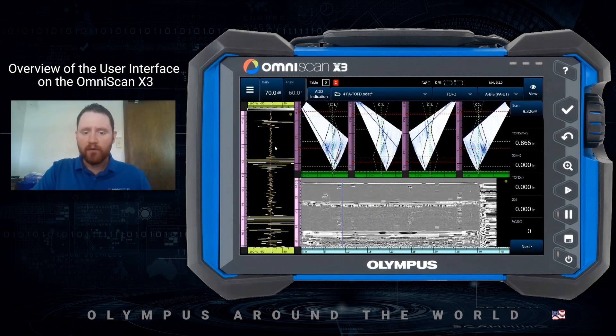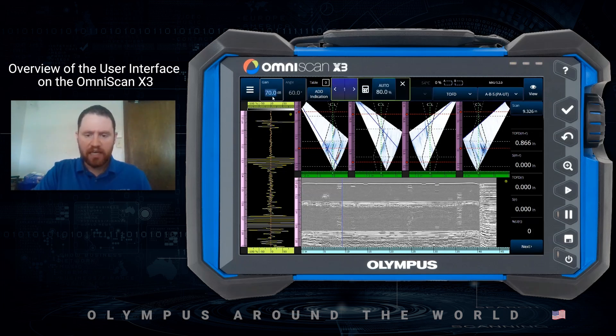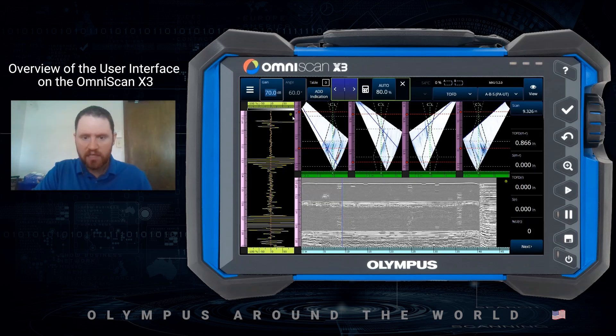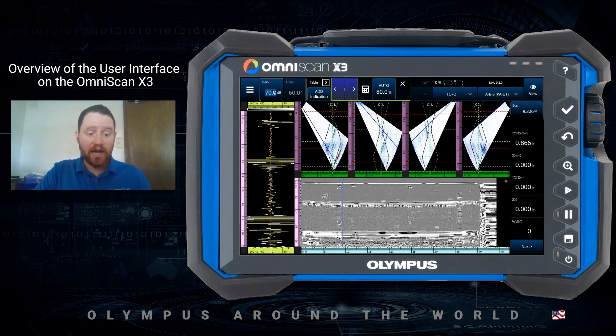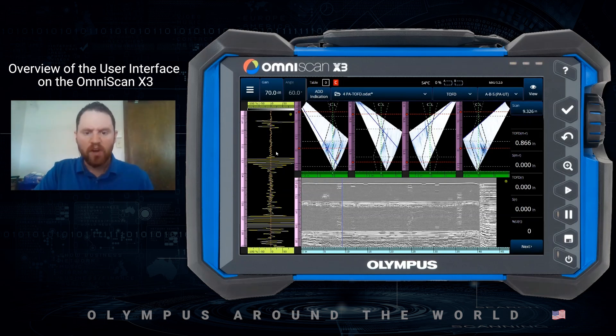Moving on from the main menu to some other portions of the software, the first we'll focus on is the toolbar across the top — your quick access functions. We have access to the gain, where I can click and change the gain for whatever group I'm currently looking at, which is indicated by the green dot on the displays. I can see the A-scan for the active group, and another green dot indicates which display the A-scan is coming from. I also have a couple of different ways to identify where the A-scan is coming from via the group button on the toolbar.